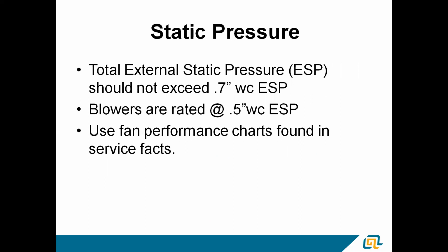Total external static pressure on our Trane American Standard equipment, and I think you can apply this across the board, should not exceed 0.7 inches of water column. All the blowers in the Trane American Standard equipment are rated at 0.5 inches of water column. In other words, the blower will develop the advertised airflow. So if you've got a 3-ton drive, you can get 3 tons out of it if you're working against 1/2 inch of static. As that static pressure increases, the airflow is going to go down.